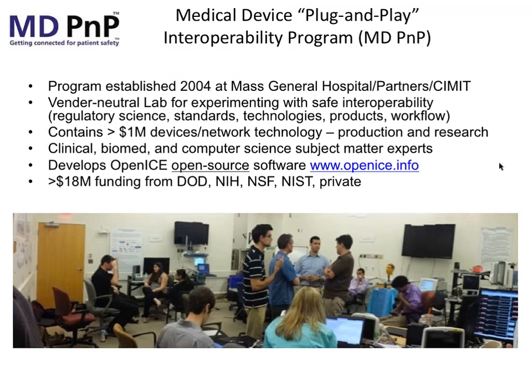We started our program on medical device interoperability in 2004, following the OR of the Future project here at Mass General. We've developed a vendor-neutral laboratory over the years with about a million dollars of infrastructure of medical devices and networking technology, both production and research. We've developed an open source platform for research purposes — for use by manufacturers and others working on standards and interoperability device integration — at openice.info. Our funding has been primarily from federal agencies.